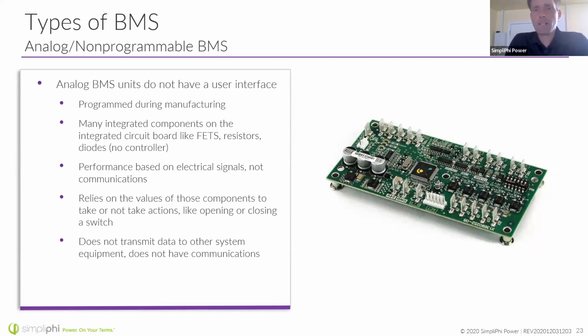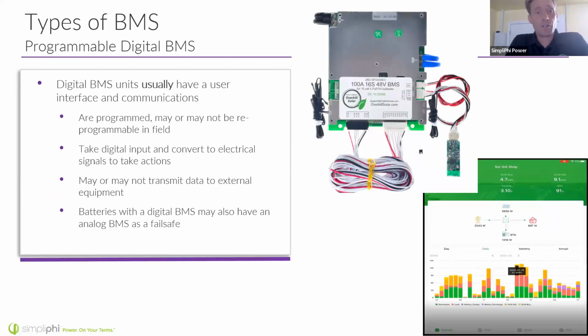Analog BMS systems basically do not have user interfaces. Their values are programmed during manufacturing. It's basically designed to operate under a set of circumstances that are controlled during the manufacturing process. And they don't have as many integrated components, such as programmable chips, etc. Their performance is based on electrical signals, and not communication signals. They typically rely on the values of the components to take or not take actions, and they often do not transmit data to other systems or equipment that might be in an energy storage system.